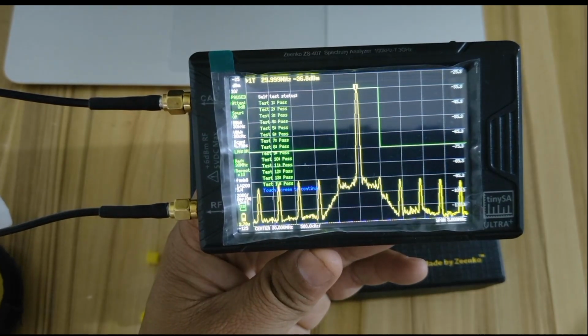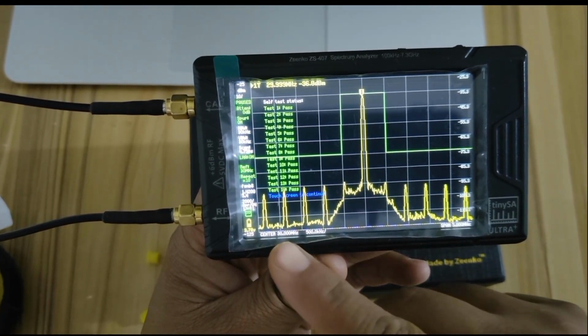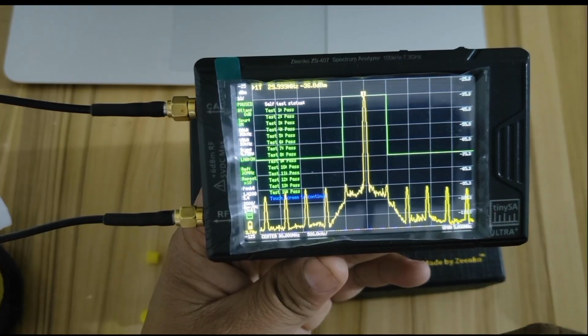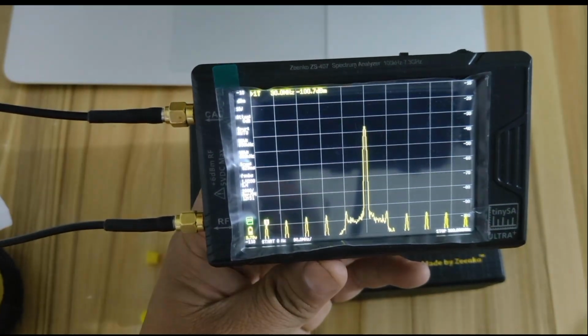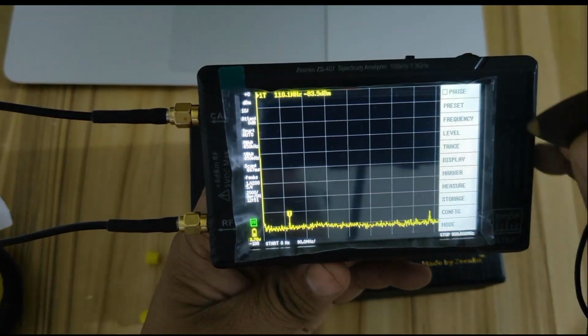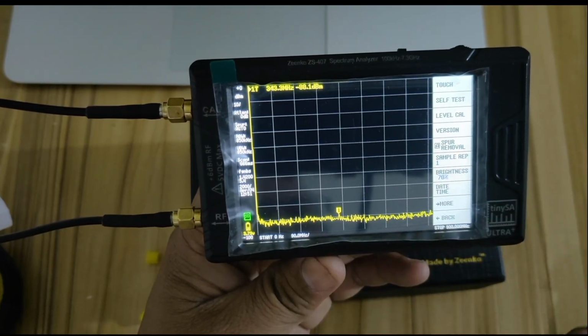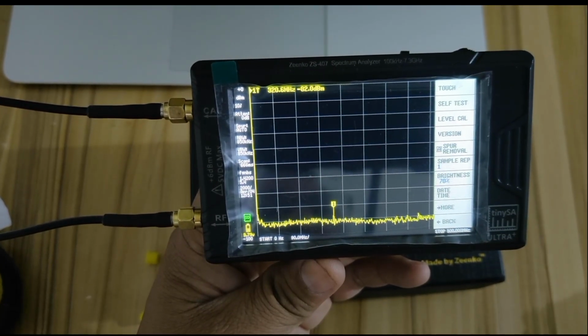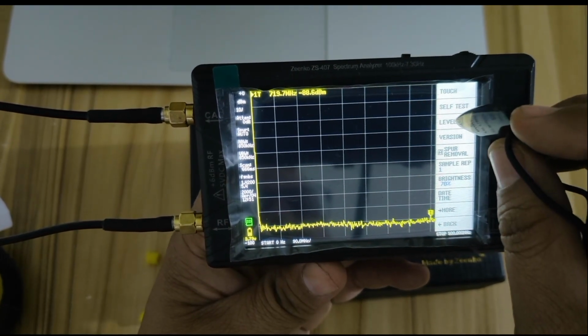And we're waiting for test number 14. After this, it will tell you that all the tests are passed. Just touch the screen. That's the first thing you need to do. Touch the screen again. Go to config again. And once you go to config again, now you need to calibrate this device. So go to level cal.